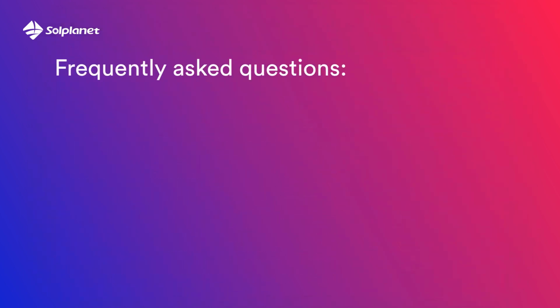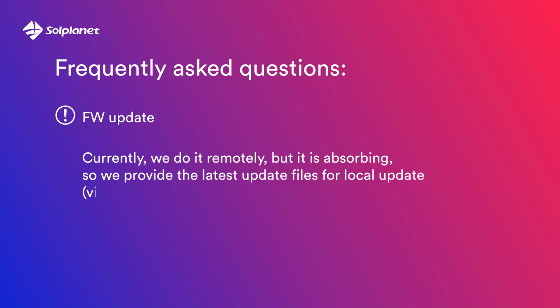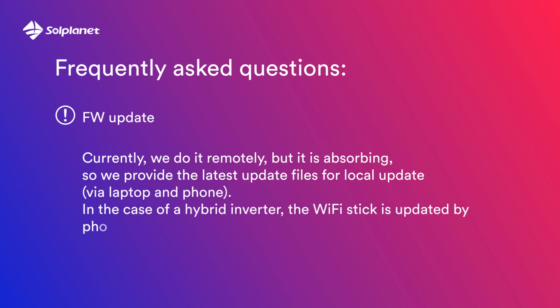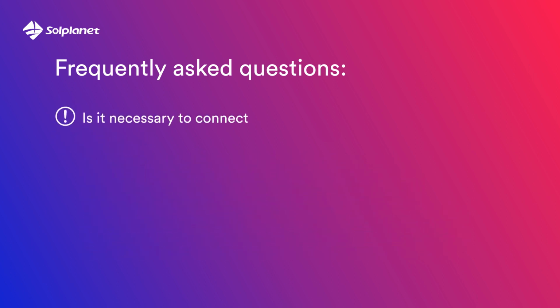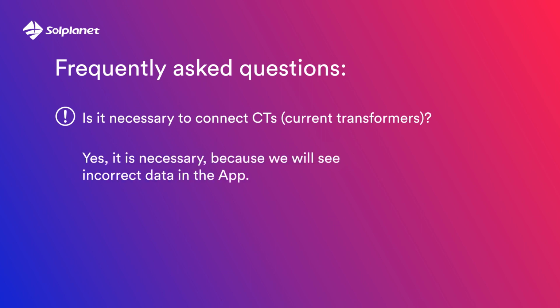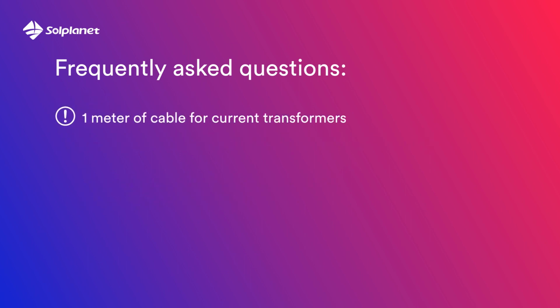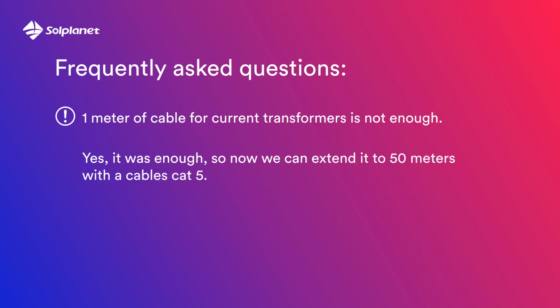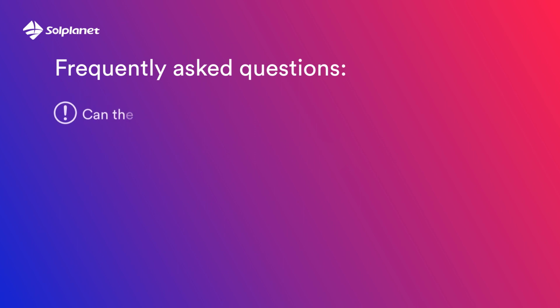Common questions. Firmware update? Yes, we can update online via the service. We can also update locally; we have a manual on how to do it. Do you need to connect current transformers? Yes, you have to. If you do not connect current transformers, then you have incorrect data in the app and cloud. Length of CT wires: you have up to 50 meters, cable 24 AWG.